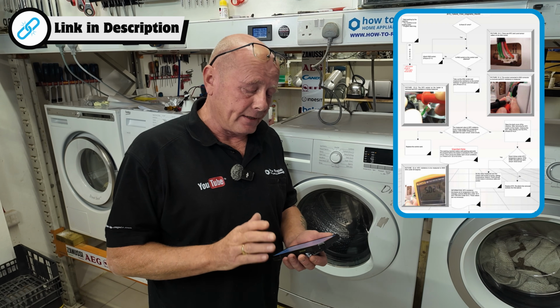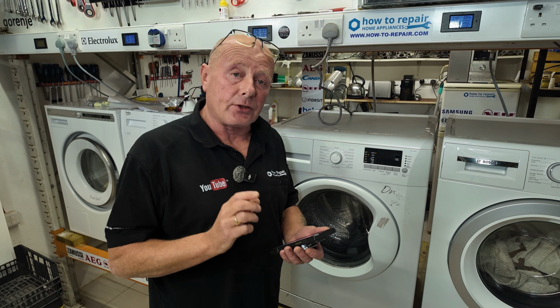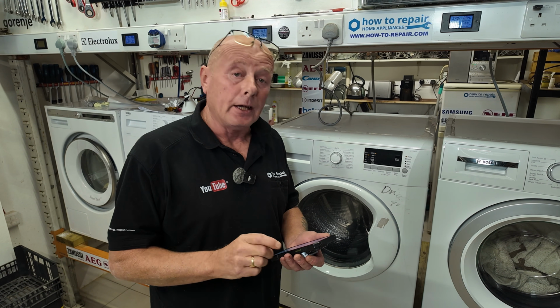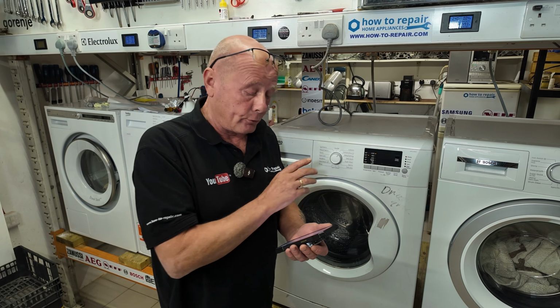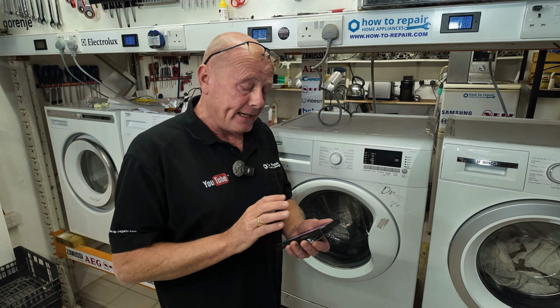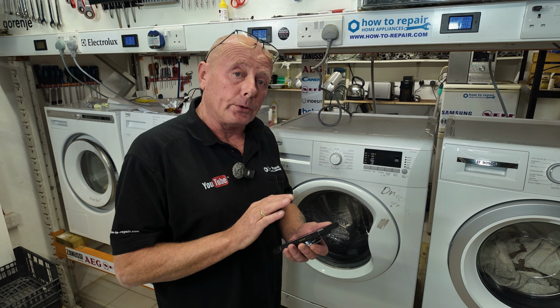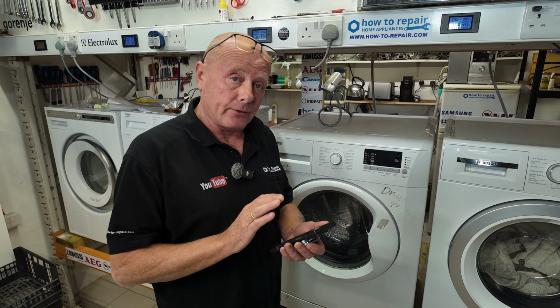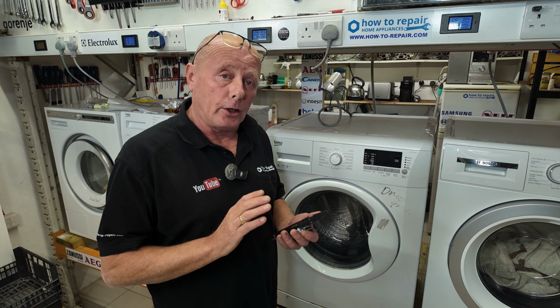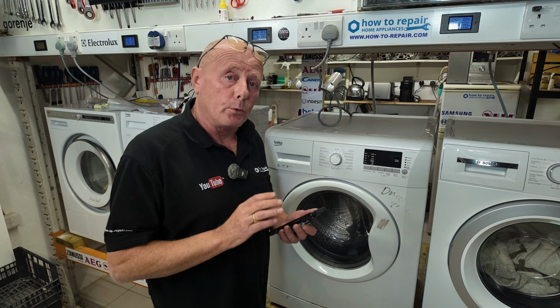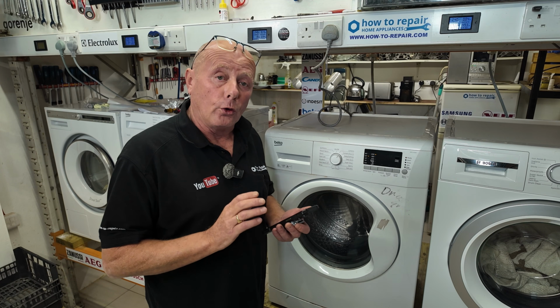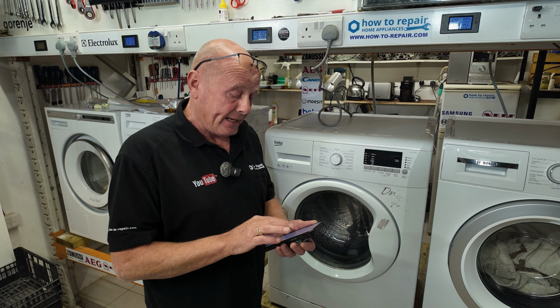E01, NTC temperature related faults. This is the NTC sensor on the heater that tells the circuit board what temperature. E02, heater related faults, and also E03 is heater related faults. This may be the heater open circuit, or you have a problem with the relay on the circuit board or the wiring related to the heater.